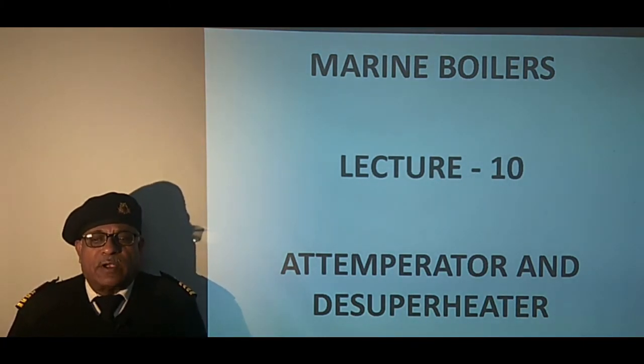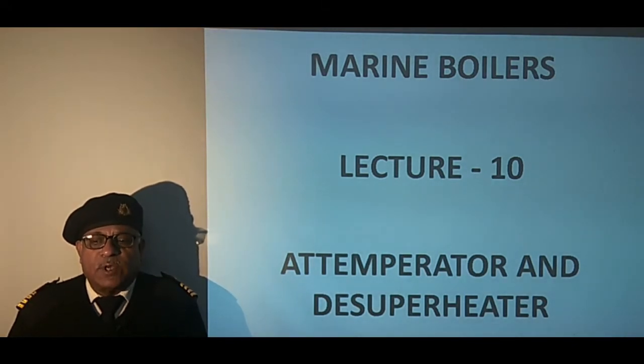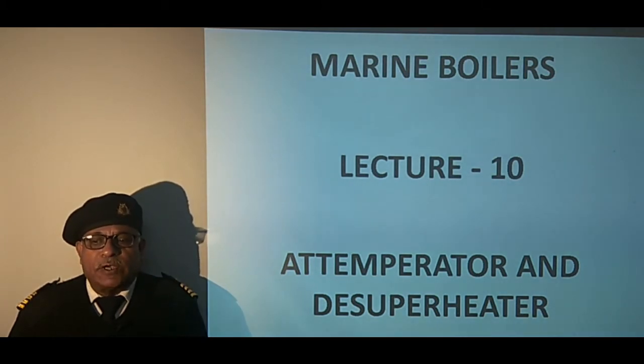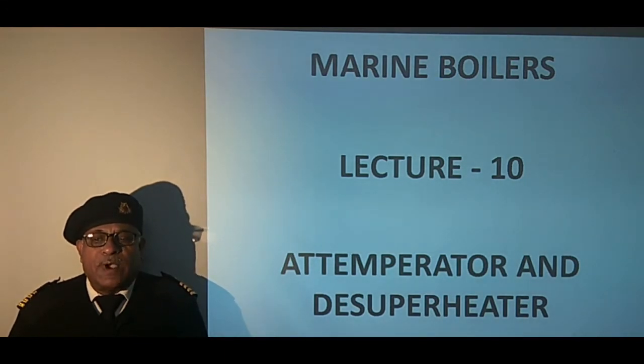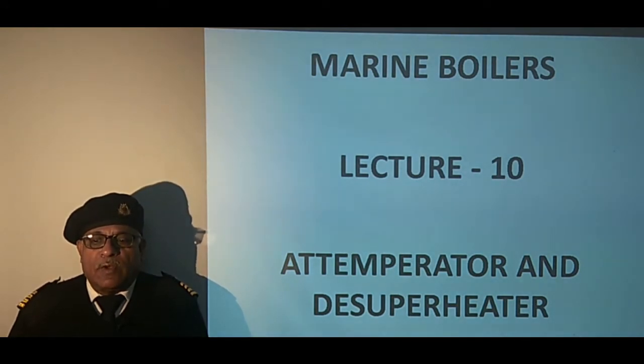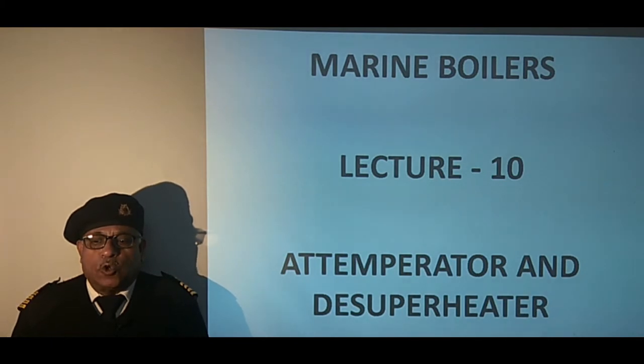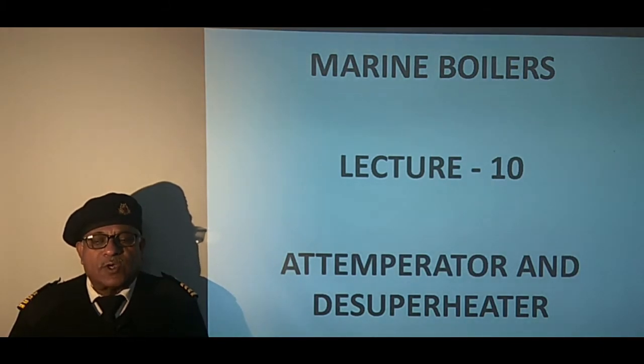A question can come to mind: why can't saturated steam be taken directly from the steam drum, and what is the need to superheat first and de-superheat it later? This practice is used to prevent damage to the superheater, especially at low load conditions when the requirement of superheated steam is small, such as during ship maneuvering. This practice ensures adequate flow of steam through superheaters so they do not get overheated due to starvation of steam.